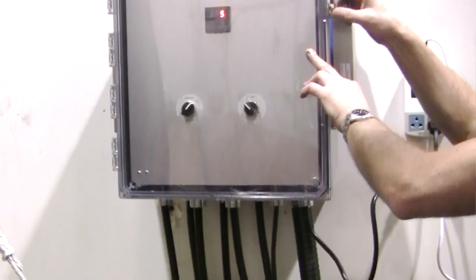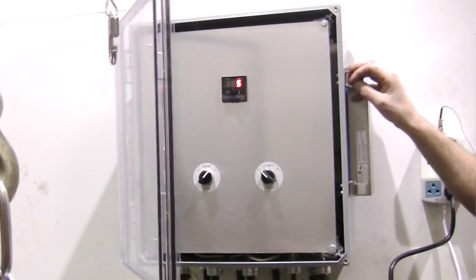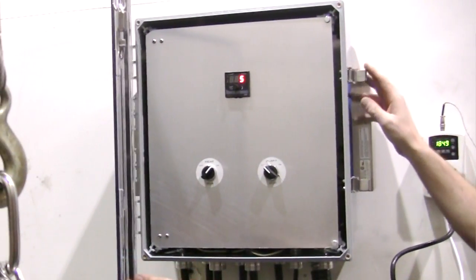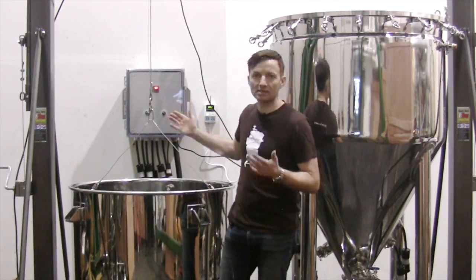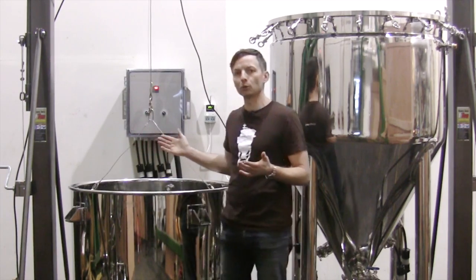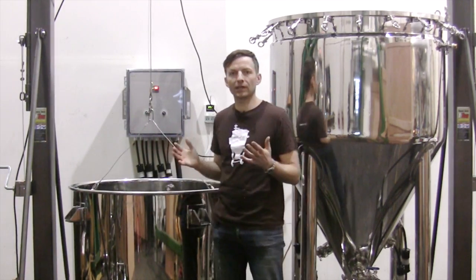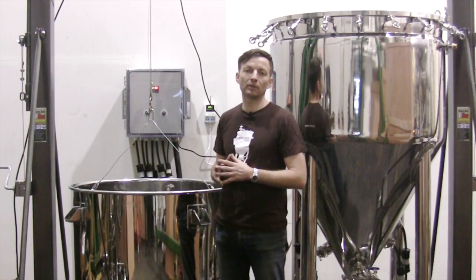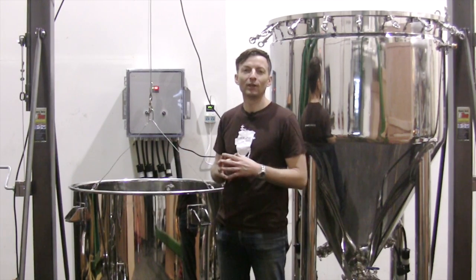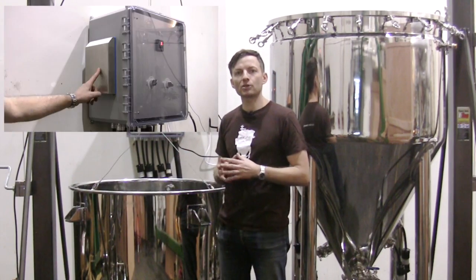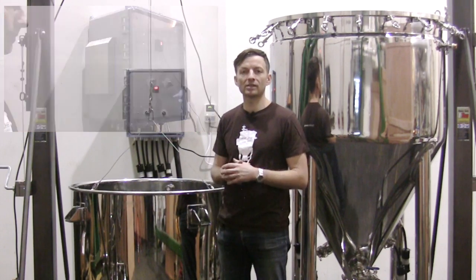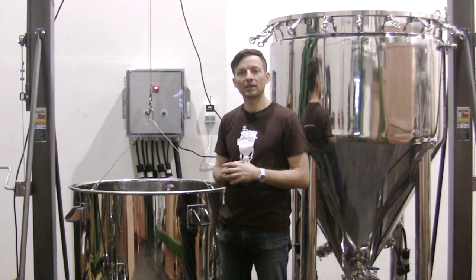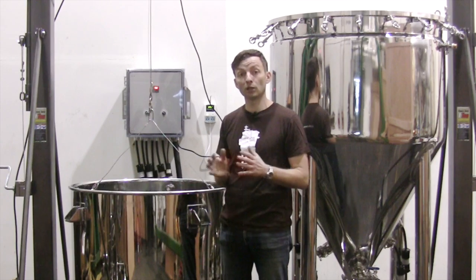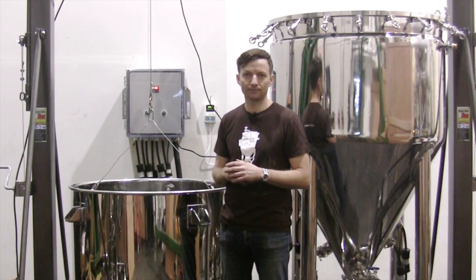Off to the side, we have installed the Brewha PTC Power Box. The PTC Power Box is a simple, rugged, and dependable brewing controller in a watertight enclosure for splashdown environments like your brewery. With a watertight box and splash-proof fan air intake and exhaust, and liquid-tight cord grips, accidental overspray when cleaning will not damage your sensitive electronics.